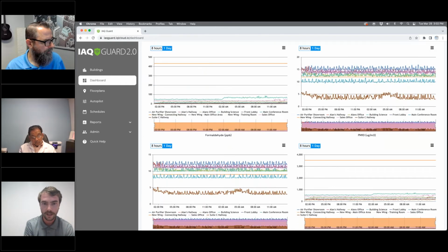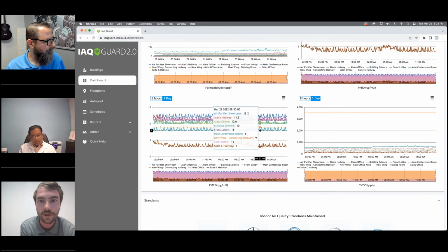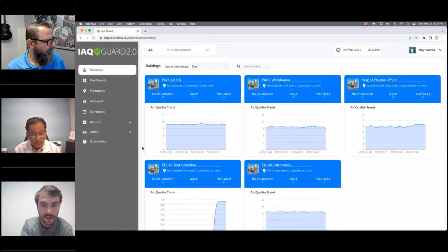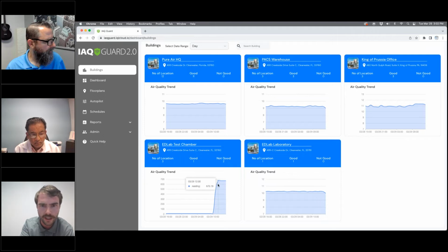And Troy, if you want to go back to the buildings tab real quick, we can look at the overall approach again. You'll notice that we have different guards linked up in each of the locations of our buildings. Once the dashboard populates here, you'll notice that for the ED lab test chamber, we have one good reading and two not good readings. That makes a whole lot of sense because we are constantly running experiments in this test chamber. We have one outside air monitor that we can keep an eye on and use as a baseline during our experiments.